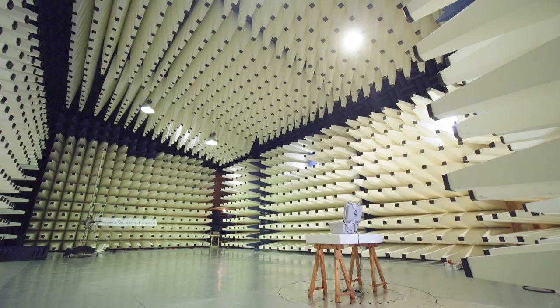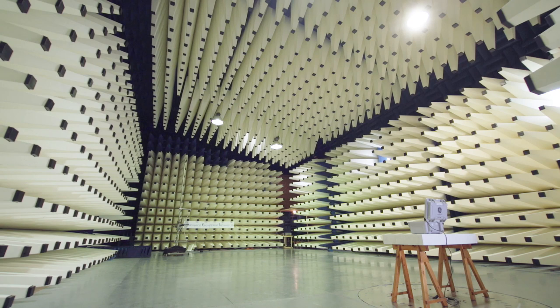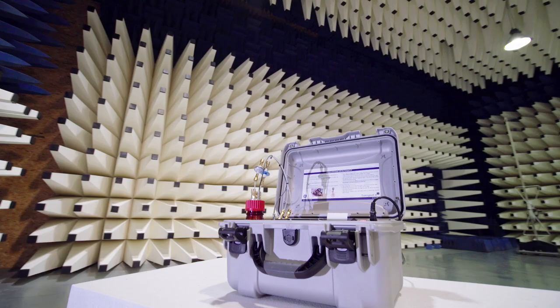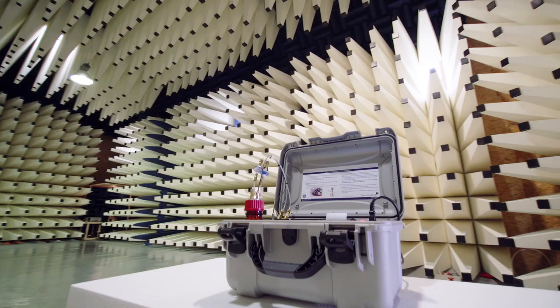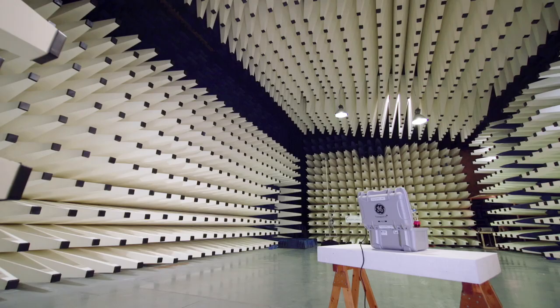Okay, so what tests do we conduct here on the GE products? Here we do EMC testing, to ensure that your product complies with European and international regulations. Okay, nice. So what's EMC exactly? EMC stands for electromagnetic compatibility. It means that the product doesn't produce excessive levels of radio frequency interference and isn't susceptible to external interference. So is that what the cones here are for? What do they do in this room? The cones are absorbers. This is a shielded room to keep out background radio frequency signals and to prevent reflections off the walls.